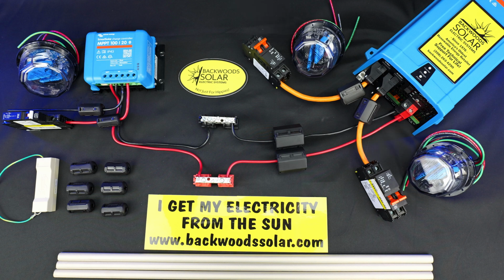Using our small-scale mock-up here as an example, we essentially have 2 pieces of equipment within this system we want to protect: our solar charge controller and our inverter. While the exact placement of your SPD or ferrites within your system may vary, the general concept is we want to place them as physically close to the equipment we're trying to protect as possible.